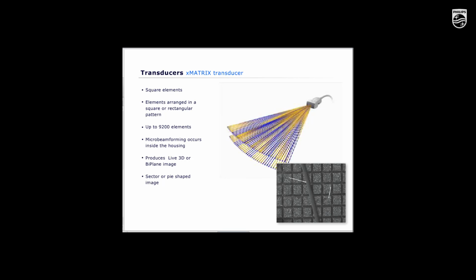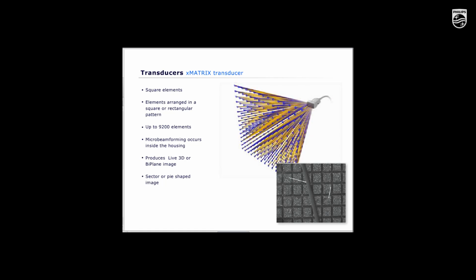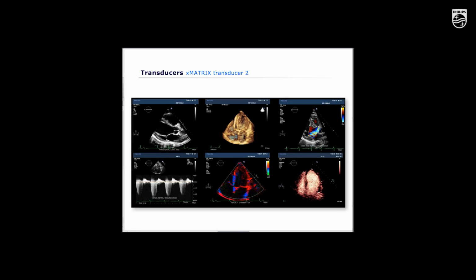With the X-matrix transducers, you can control the beam in any direction using X-plane. Initially, these transducers were developed for echocardiography. Now they can also be used in general imaging as well. Depending on the type of X-matrix, you can use all the modes with one transducer, whether it be 2D, 3D, or 4D, which is live three-dimensional imaging, live X-plane, Doppler, or color Doppler.